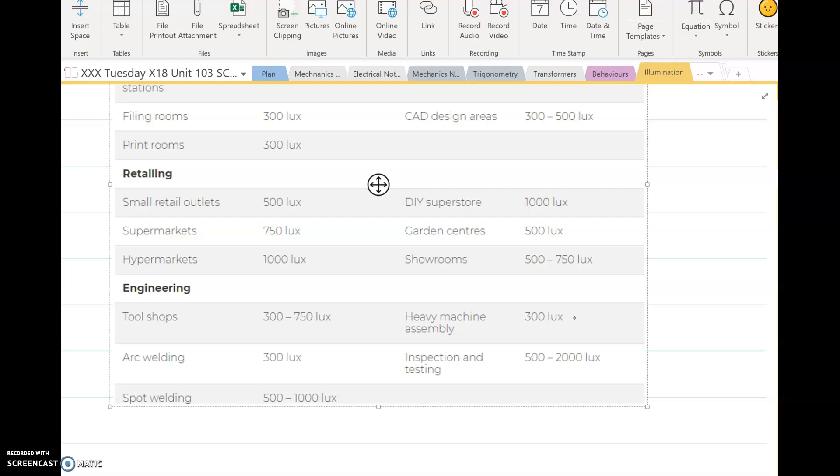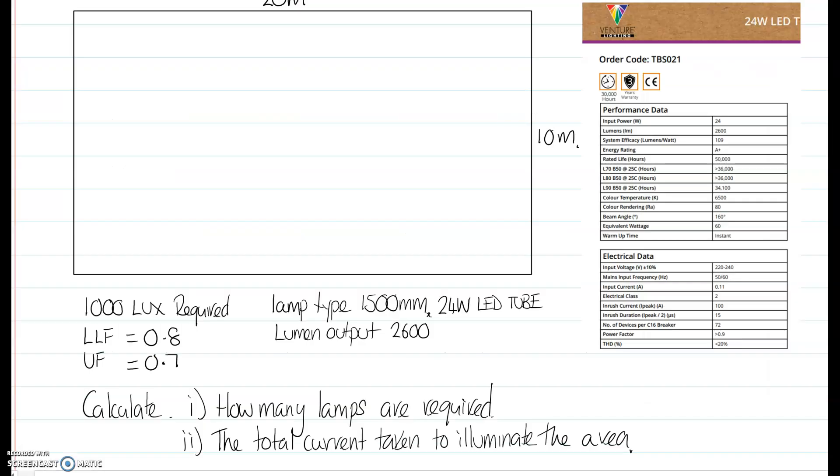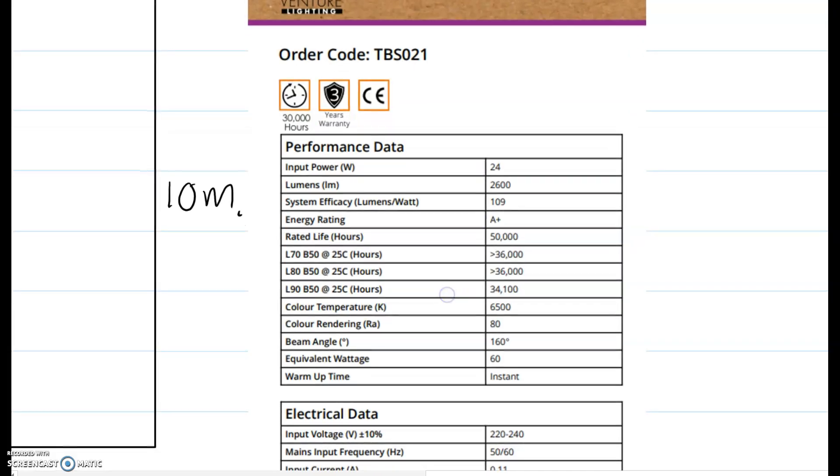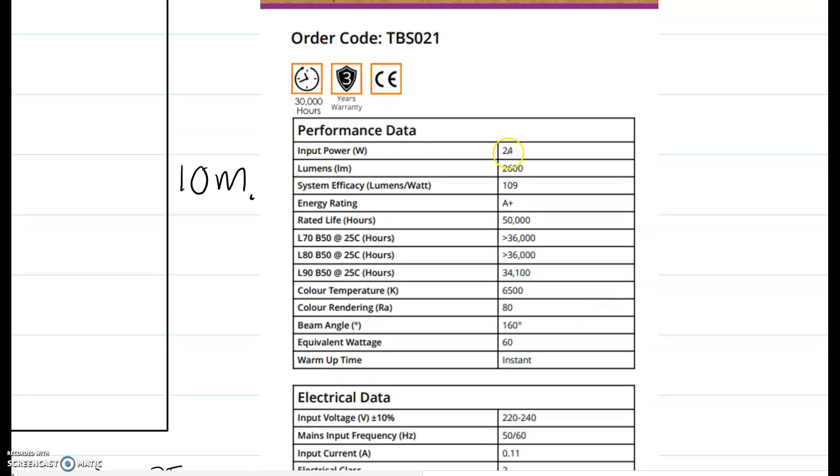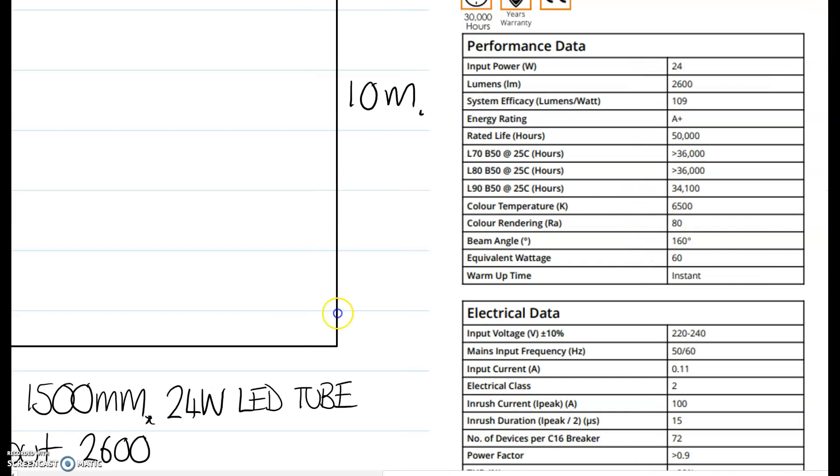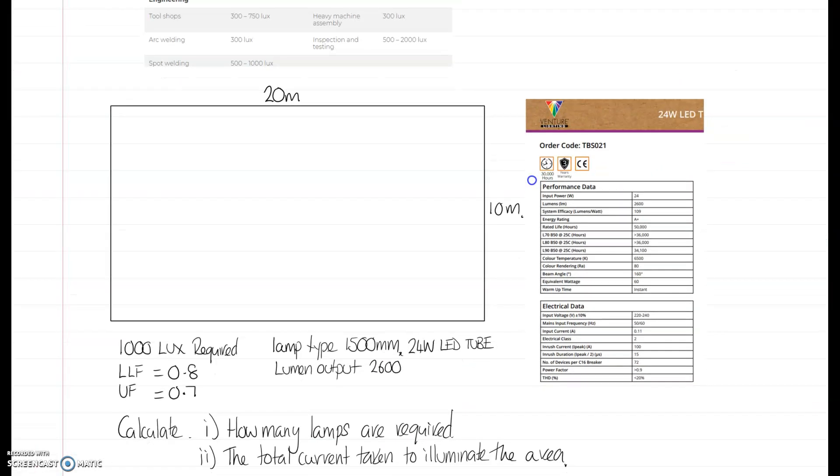Let's look at an example then, and we're going to simulate a workshop area and work out how many lights we actually need to illuminate an engineering workshop up to a value of 1,000 lux. So we have a factory floor or workshop floor of 20 metres by 10 metres, and we're going to use a 1,500mm 24 watt LED tube. I've gone online, just literally searching online for LED data. You can see this is a 24 watt input power, and the lumens is 2,600. The efficacy, lumens per watt, is 109. It also tells you about the colour temperature, so it's nice and cool. 6,500, that's going to be a nice white, clear light.